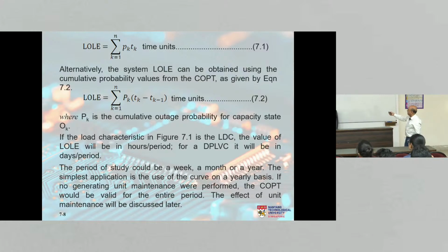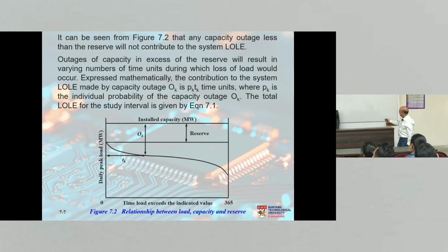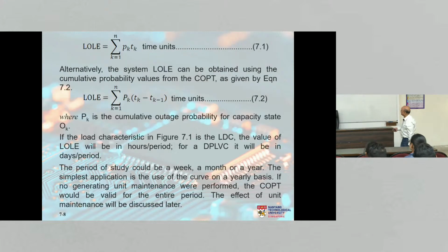So this is the equation for LOLE, summation Pk Tk. We can also use the cumulative probabilities. It's a question that you have been asking, how do we get this into play? We can use the cumulative probabilities, then the LOLE will be the summation of capital P k times Tk minus Tk-1. So then you have to find the difference of the time units because you are using cumulative probability. If I go back to this one, suppose this is T1 and then we'll have a T2 here. If we use cumulative probability, it will be T2 minus T1, the difference of the time units. We'll see the example and then I'm sure you will understand it better. So if the load characteristic is the load duration curve, the units for LOLE will be in hours per period.